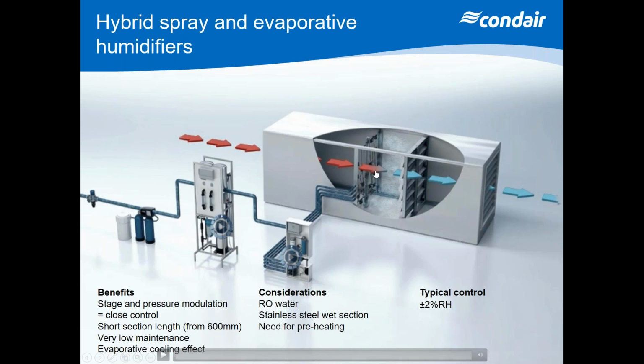But the clever bit about it and the way it's using two types of technology is that we're spraying water, but then any that hasn't been evaporated gets caught on a ceramic matrix, which then evaporates it off as the air travels over it in the same way that an evaporative humidifier does. So we're not getting the wastage that you do with a traditional high pressure system. So I can have a short section length, 600 mil between those two sections. I've got to have a stainless steel section in there because it's a wet section, but it will give me that close control and utilize the adiabatic system.